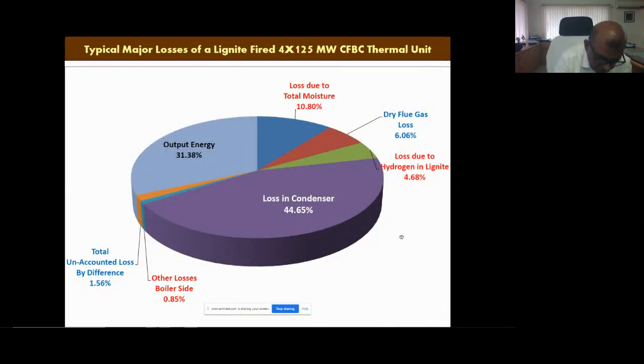Now we come to our main focus point, efficiency. When we talk about efficiency, we mean output. Whatever input we are giving, the output is the input minus losses. And if we manage the losses, the efficiency will improve. In a thermal power plant, as all the distinguished guests and people present here know, the major losses are in the condenser, and in our case it is around 44.65%, because it is based on the actual.